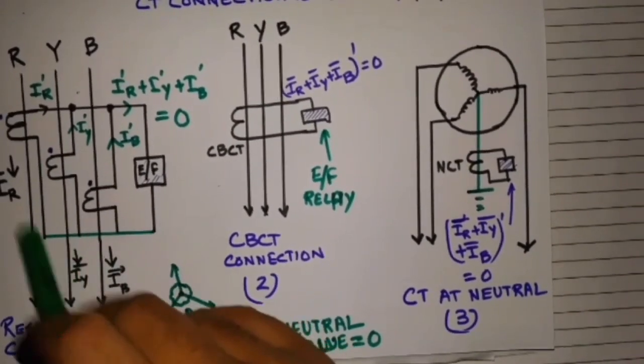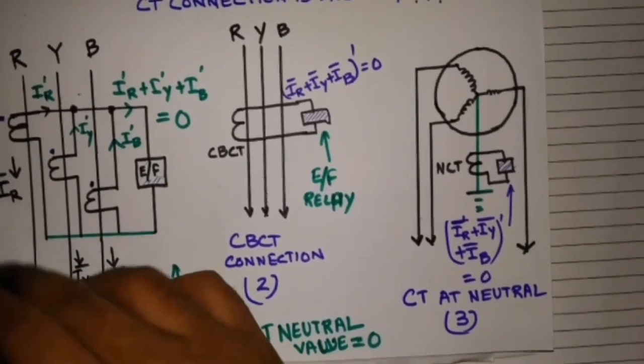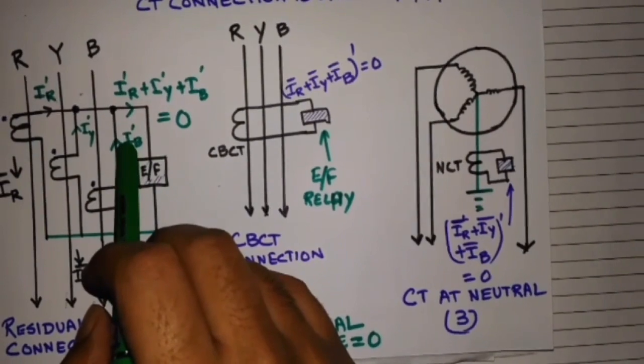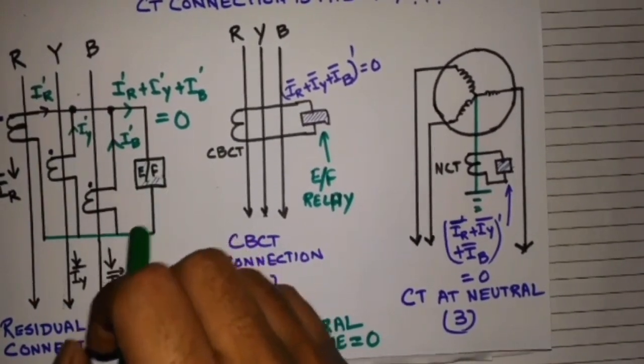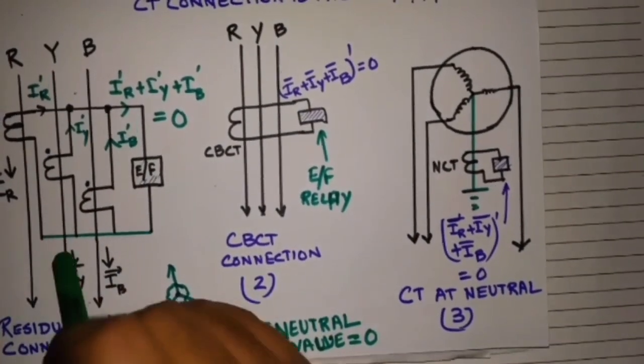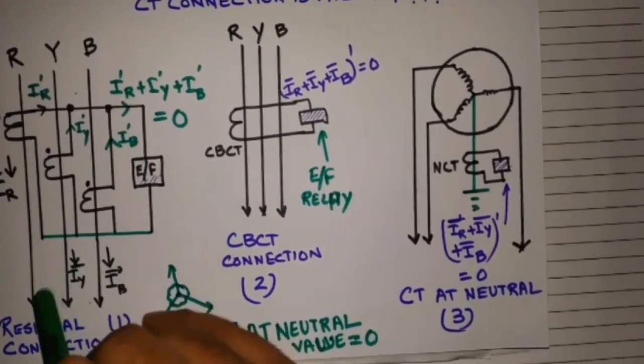But if there is an earth fault, suppose there is an earth fault in IR, so IY and IB will be zero and only IR will have a value. So here IY dash and IB dash will be zero, only IR will flow through the relay to energize.